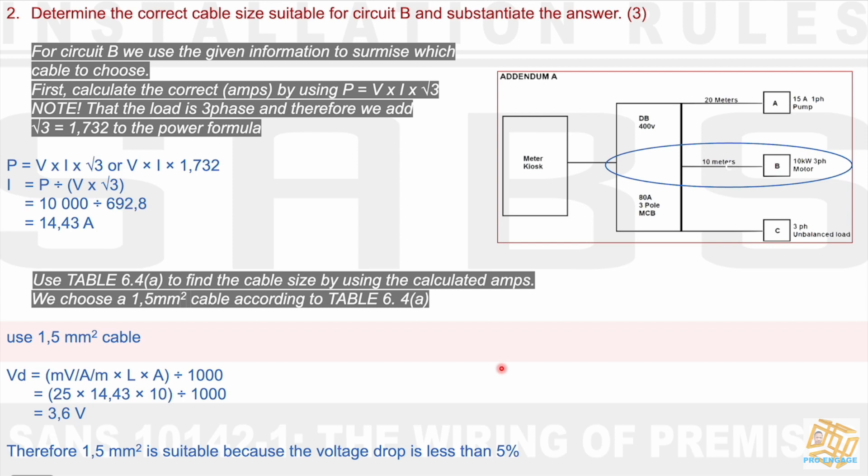We then use table 64A to find the cable size by using the calculated amps. Again, we've done this before. We choose a 1.5 mm² cable according to the table 64A. We use 1.5 mm² cable, and we say if we use that, we then go to the table, find the 25 value according to this and the table and its column, and we times that by the amps and distance, and we divide it all by 1,000 to convert that answer to volts. 3.6 volts is the answer. Therefore, 1.5 mm² cable is suitable because the voltage drop is less than 5%.